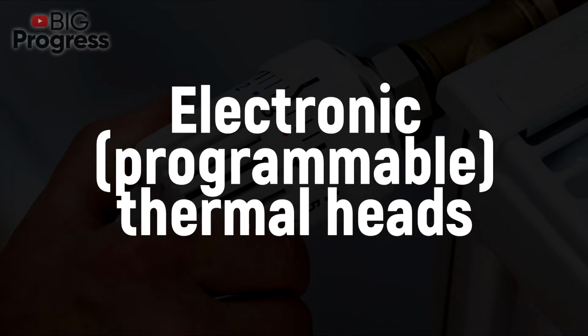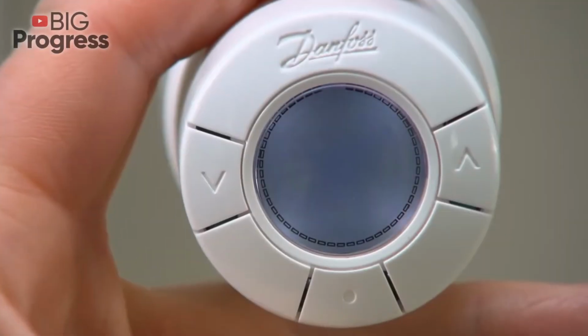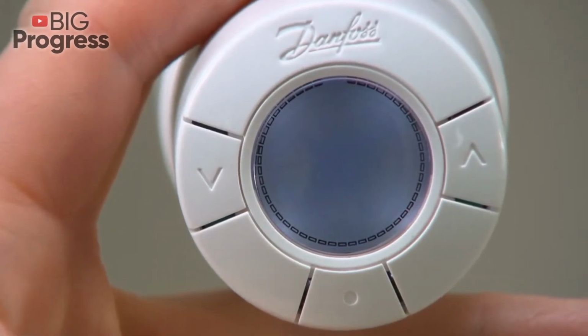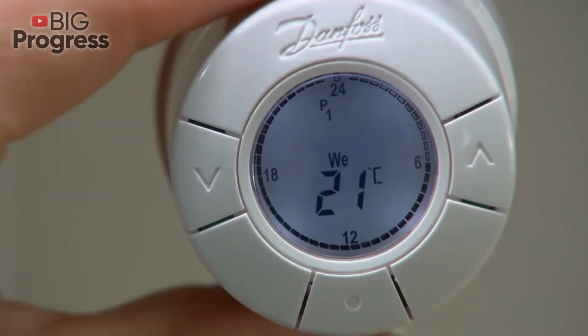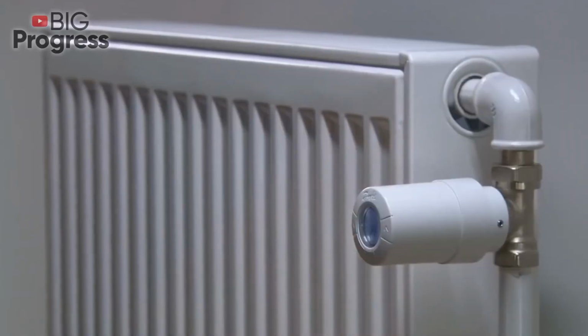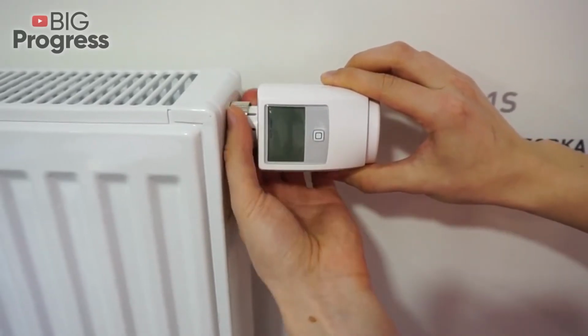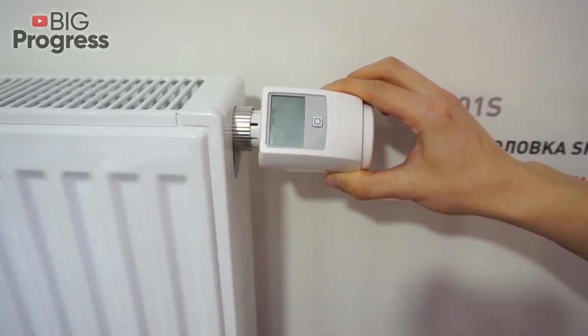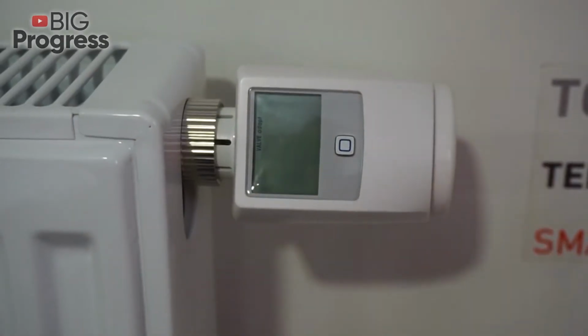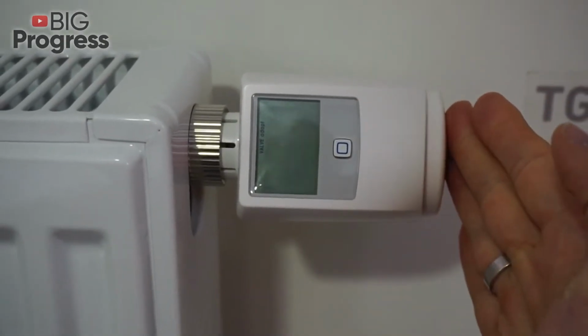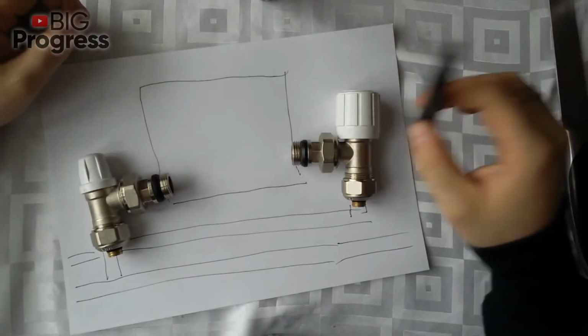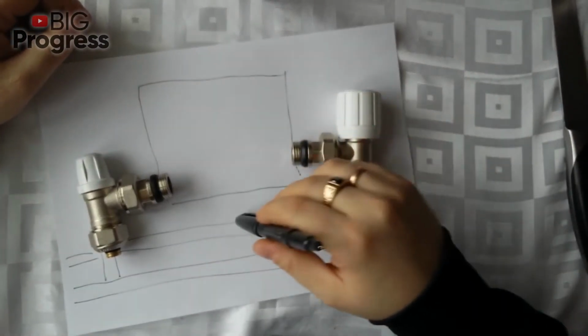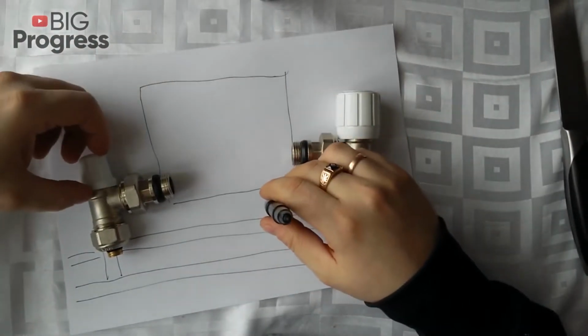Electronic programmable thermal heads. The difference between programmable and conventional thermostats is that the temperature sensor reacts to changes in room temperature every 1 to 2 minutes and immediately transmits a signal to the electric motor, which acts on the stem of the thermostatic valve that regulates the supply of coolant to the radiator. Thus, a very precise and almost instantaneous regulation of the coolant and the heat transfer from the radiator takes place.